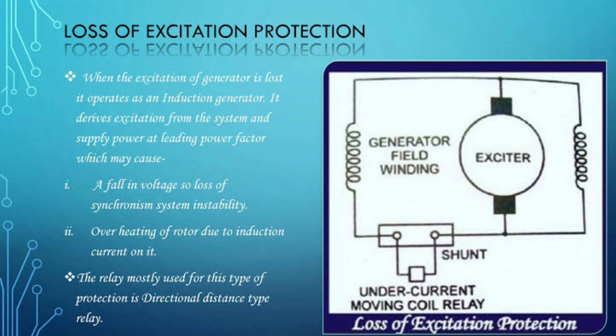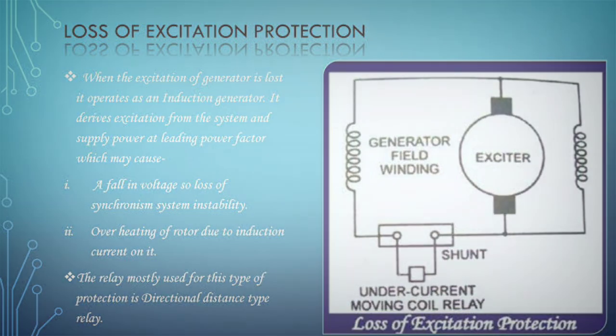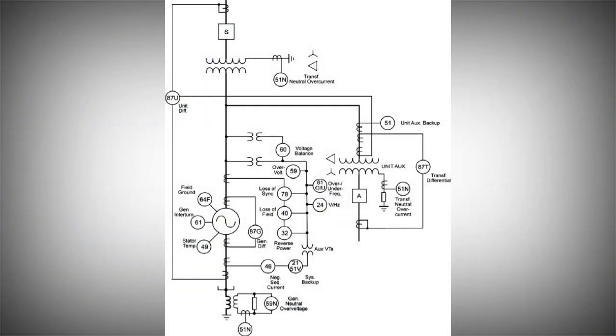How can we prevent the insulation damage? The generator sets an excitation limit in the protection relay. So if the excitation value is low in real time and the excitation limit is reached, the protection relay issues a trip command and we open the circuit breaker. This way the generator is isolated and the fault is cleared, preventing heat damage.